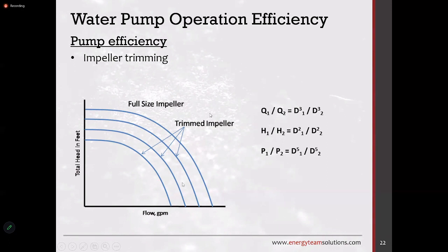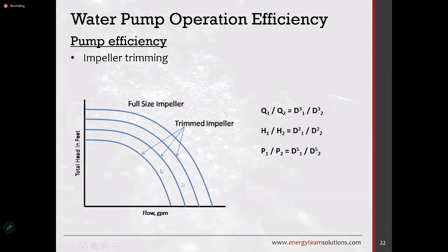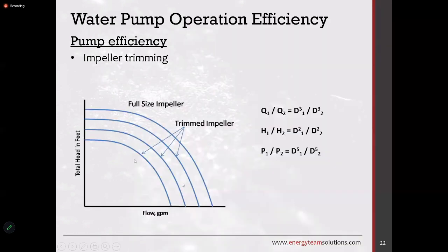So if you do an impeller trimming, you cut it off. It is a bit dangerous. You can't paste it again. So there is a risk of doing it incorrectly. The only advantage is it is cost effective, whereas VSD could be very expensive, as you need to install it. When the impeller is getting trimmed, the pump curve comes down. When the pump curve comes down, you can select a pump which is suitable to your system curve at the best efficiency point.